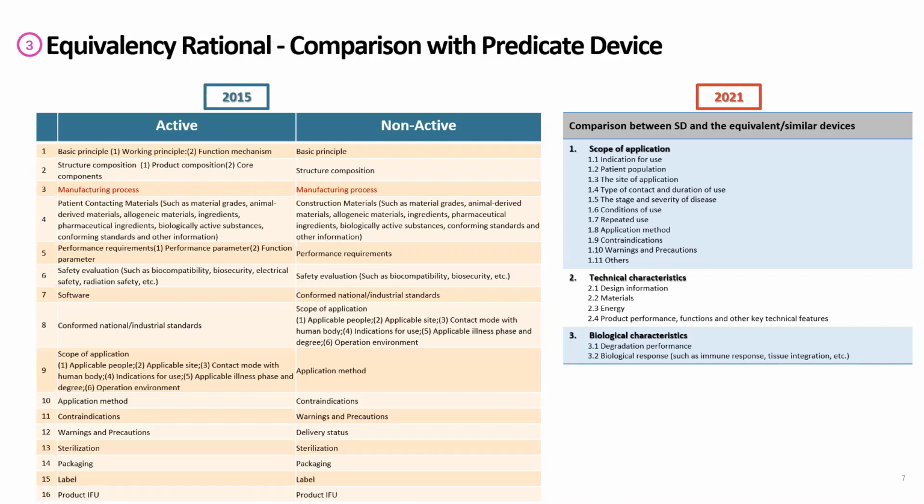And the second is about the patient population. I'm not sure, but in my experience, it's really difficult to find an age or sex limitation in the IFU of a suture device. Usually, it can fit all ages of patients. So in this new guidance, we need to emphasize and explain the sex or age with which we might use this subject device. That will be a little challenging for us.